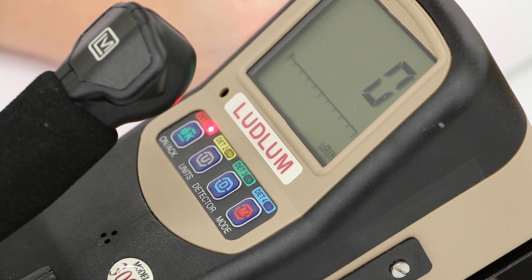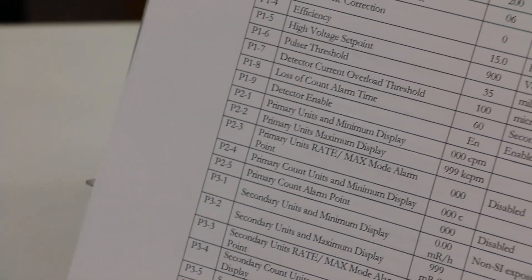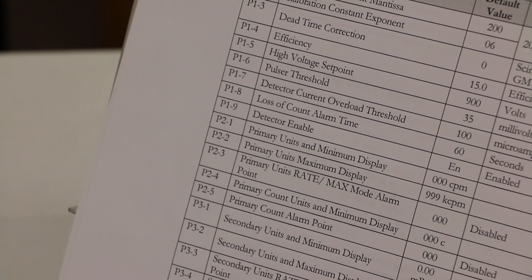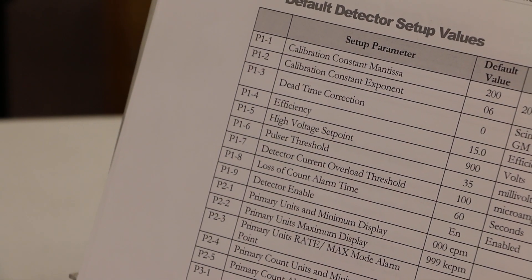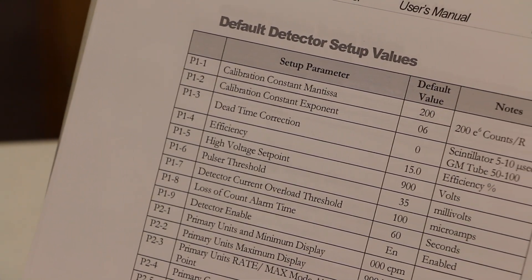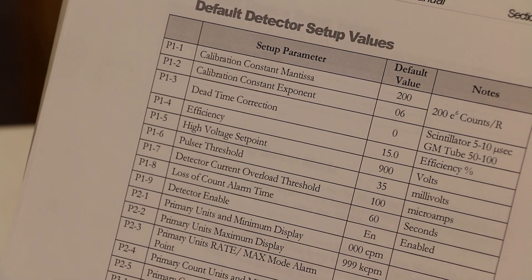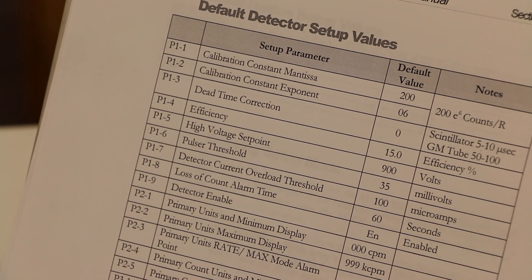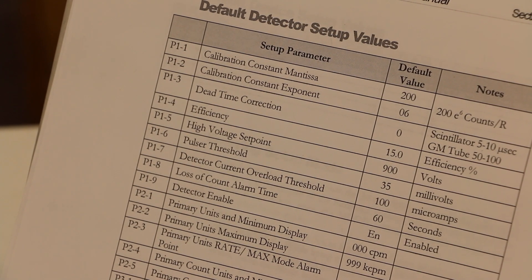Inside all of our user manuals you will find a detailed list of each parameter that is in the device menu and where it is located. If for some reason you get into the device menu and none of the digits are blinking, your instrument is probably in protect mode. Once in protect mode, you are unable to make any changes through the device menu. You can open the can and turn the dip switch to off in order to remove it from protect mode so that you can make changes.